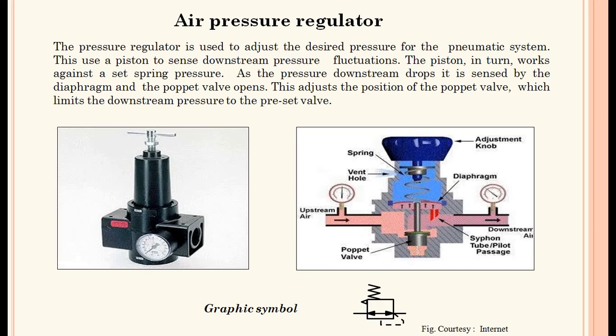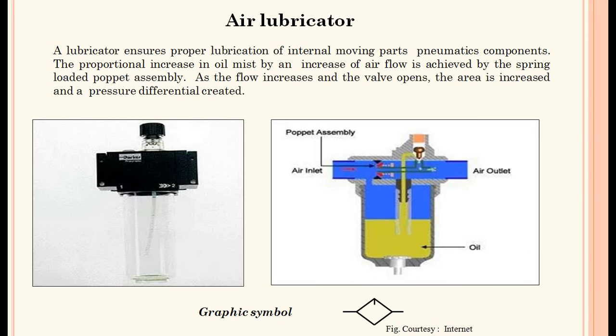Air pressure regulator — the pictorial view, photo, cut section, and symbol are shown. The pressure regulator is used to adjust the desired pressure for the pneumatic system. It uses a piston to sense downstream pressure fluctuations, which works against a set spring pressure. As the pressure downstream drops, it is sensed by the diaphragm and the poppet valve opens, adjusting its position to limit the downstream pressure to the preset value.